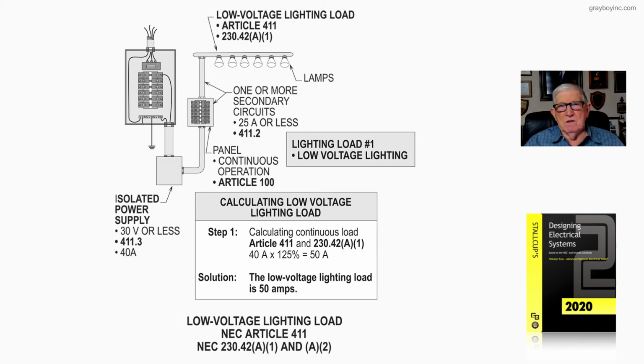And a lot of times people forget to figure those transformers that pull current and add to the load. So we are figuring the load that is listed by the rating on the transformer, because there's nowhere in the code it really says it's a gimme. So we would figure it, and that's what this figure 23-6 is illustrating.